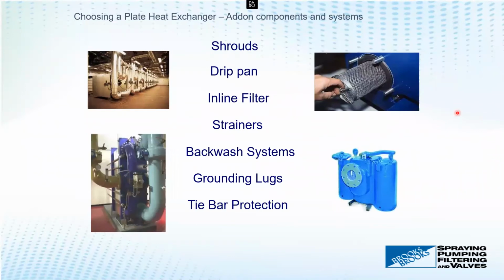So there are lots of options. Once we've got a plate and frame heat exchanger, we can handle the fluids, the pressures, the temperatures, and we like the materials — everything works great. There are some things to think about now before designing a system or putting it in. These are add-on options that are often looked at after the fact, and people go, 'if I had just known, or if we'd done this before, our system would have run great.' We would have decreased maintenance and increased runtime and efficiency of the heat exchanger.